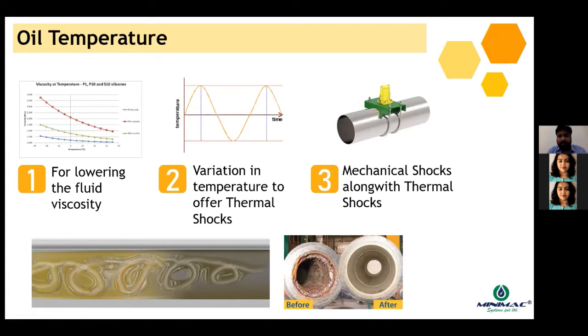The third one is mechanical shocks along with thermal shocks. So when you perform the thermal shocks using temperature variations on your lubrication system, you can also have mechanical shocks using some pipeline vibrators or manual hammers. With this, you are ensuring a better loosening effect on the debris. So down there, you can see a picture of a piping which was flushed, and you can see the difference, what happens after flushing.